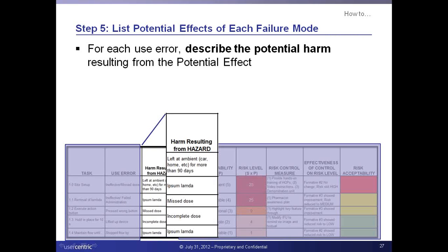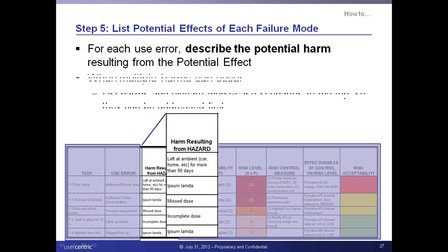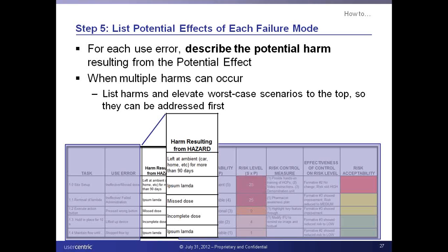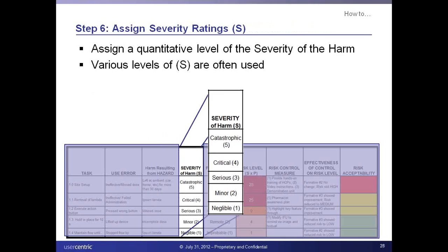Once you have brainstormed, you'll begin the process on the third column: talking about what could happen if something happened. What is the potential harm? What's the potential effect? Similar to how use errors beget other use errors, you may find harms that have a cascading effect. Address the worst case scenarios at the top and lower harm cases at the bottom. So we're breaking more rows out of the FMEA to talk about what someone could really do, or what other things they might do. Prioritize them from worst case in terms of harm, so the highest potential for harm can always be addressed first.